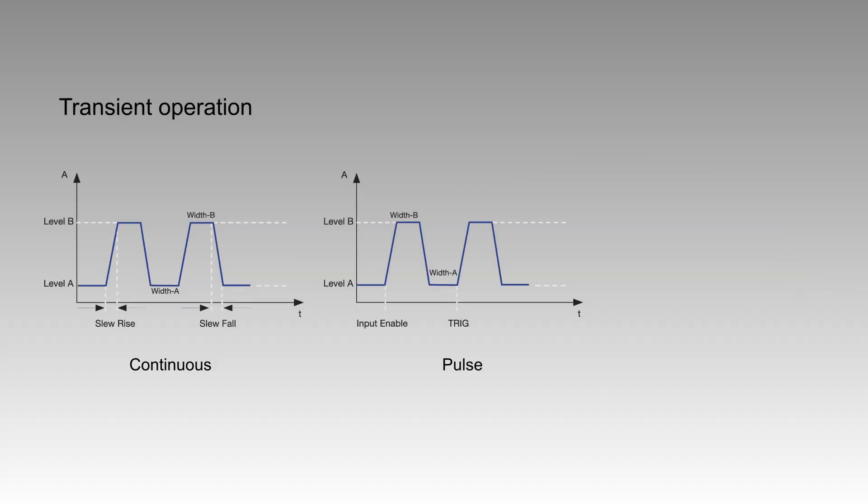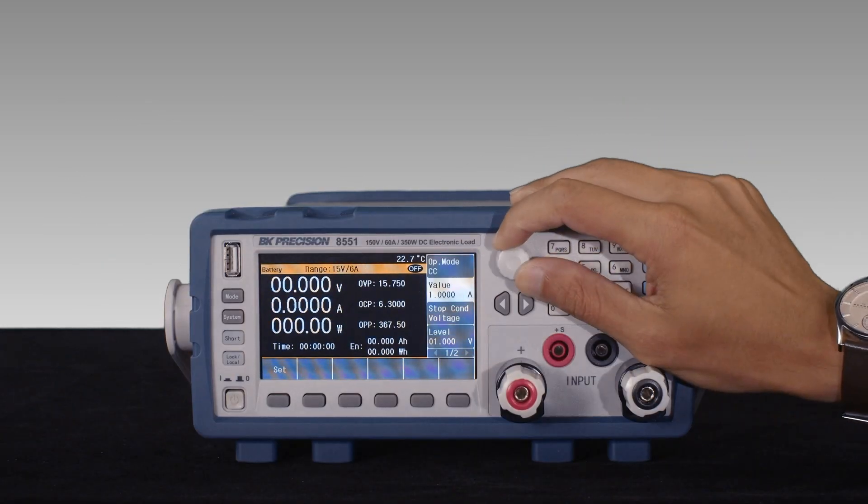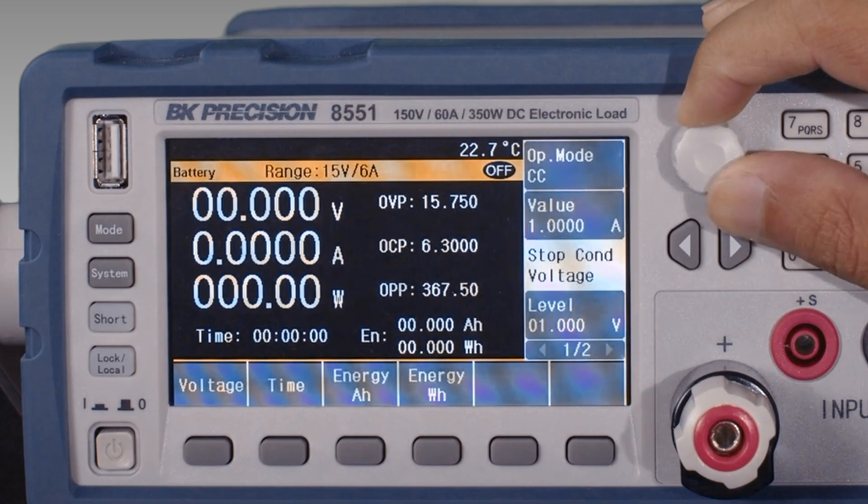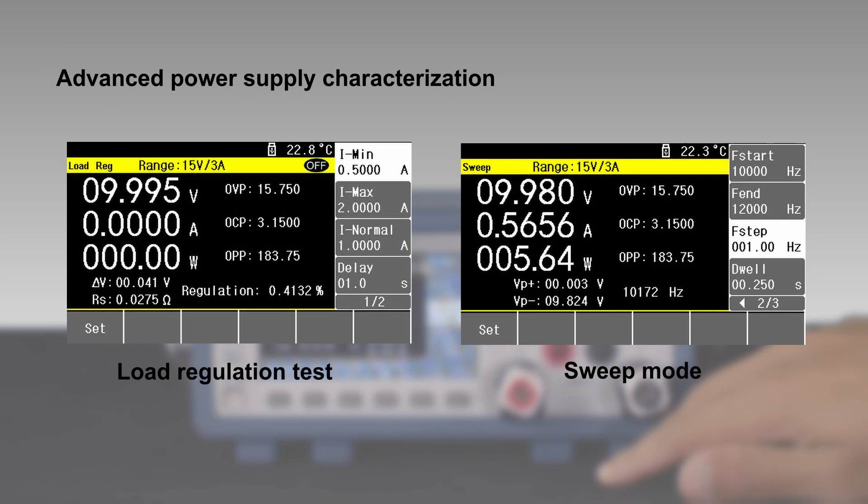Transient operation enables the load to periodically switch between two load levels continuously for one trigger-dependent pulse cycle or toggle. Additionally, this series offers advanced capabilities with a dedicated battery discharge mode to safely discharge batteries and test modes specifically designed to evaluate common DC power supply performance indicators including load regulation and maximum overshoot-undershoot.